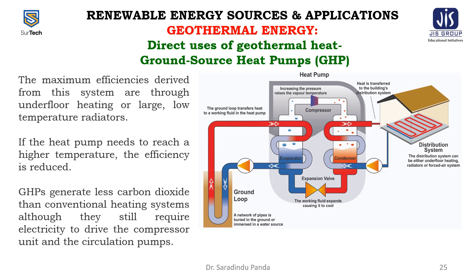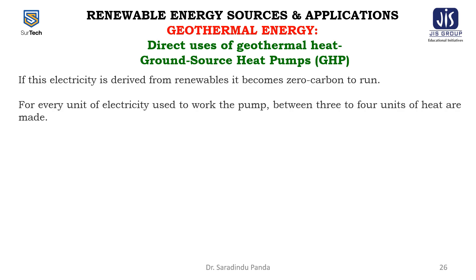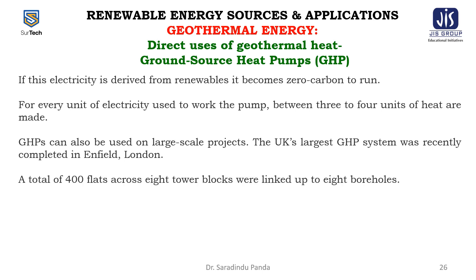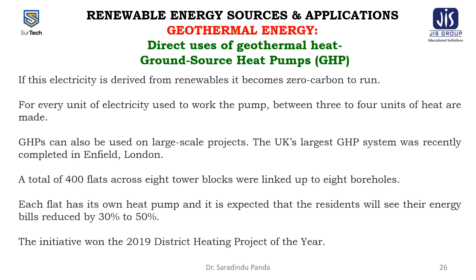GHPs generate less carbon dioxide than conventional heating systems, although they still require electricity to drive the compressor and circulation pumps. If this electricity is derived from renewables, it becomes zero carbon to run. For every unit of electricity used to run the pump, between three to four units of heat are produced. GHPs can also be used on large-scale projects — the UK's largest GHP system was recently completed in Enfield, London, where 400 flats across 8 tower blocks were linked to 8 boreholes. Each flat has its own heat pump, and residents are expected to see energy bills reduced by 30 to 50 percent. The initiative won the 2019 district heating project of the year.